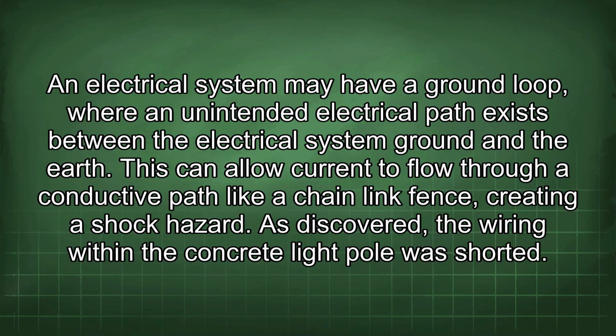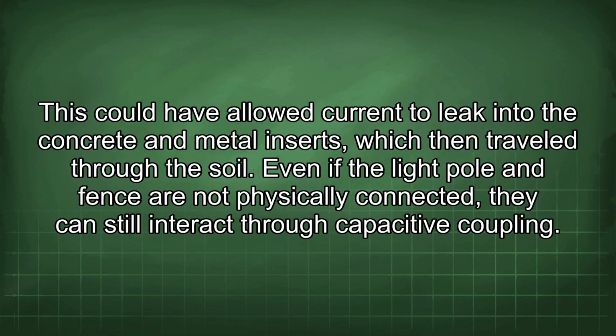Electrical system may have a ground loop, where an unintended electrical path exists between the electrical system ground and the earth. This can allow current to flow through a conductive path like a chain link fence, creating a shock hazard. As discovered, the wiring within the concrete light pole was shorted. This could have allowed current to leak into the concrete and metal inserts, which then traveled through the soil.